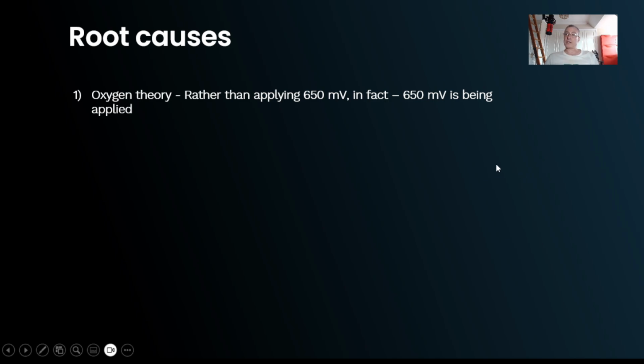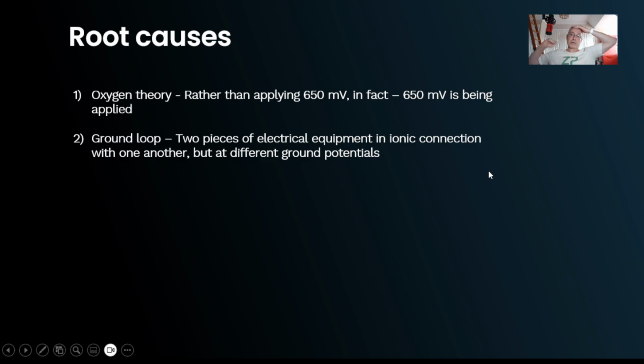There's also something called the ground loop theory. I'm hoping it's not this, but we'll find out by doing a simpler experiment. In the ground loop theory, you've got a pump and a PC system with a potentiostat on it, and those two systems are actually in contact with each other through the conductivity of the solution. One is grounded and the other is grounded, and they should be at the same ground - but if they're at different grounds, you can get a flow of current because you've got two electrical systems in electrical contact with each other.